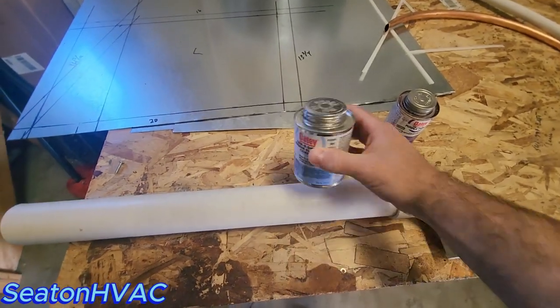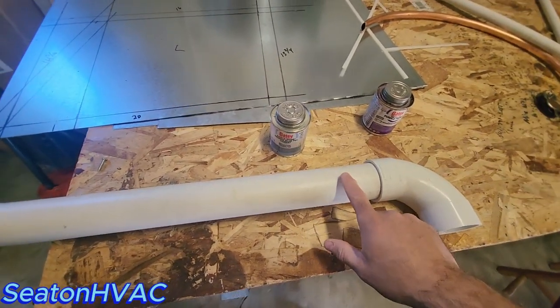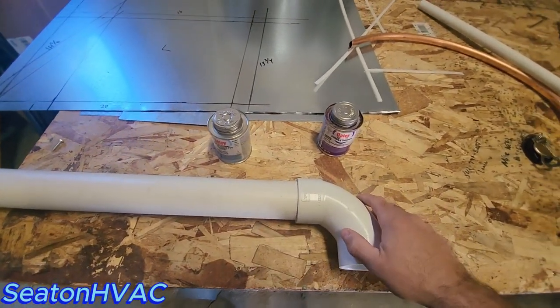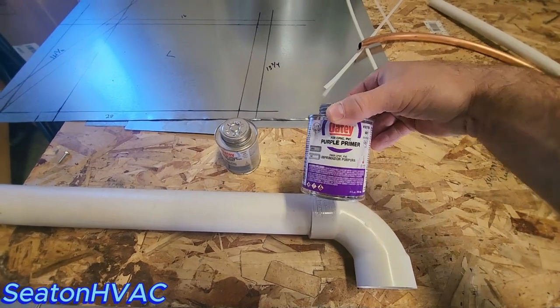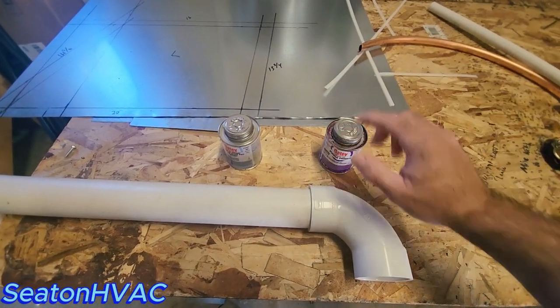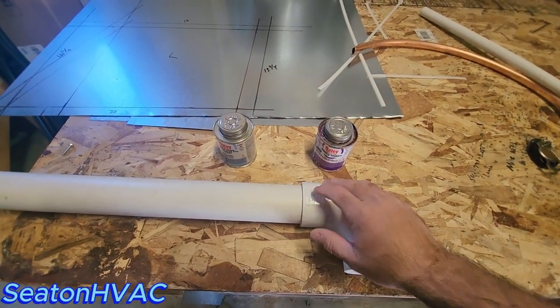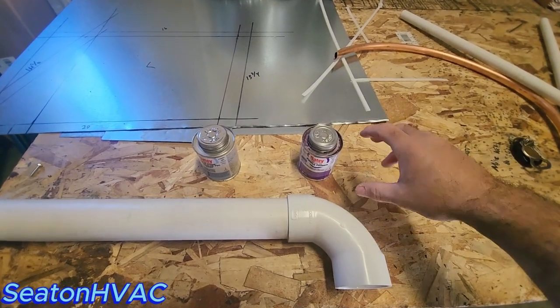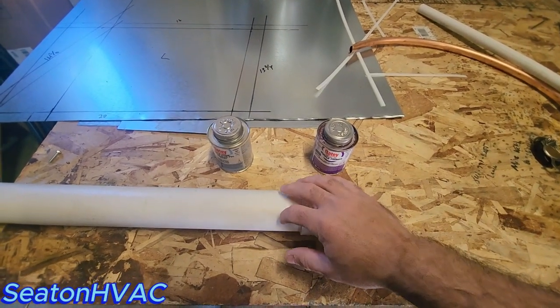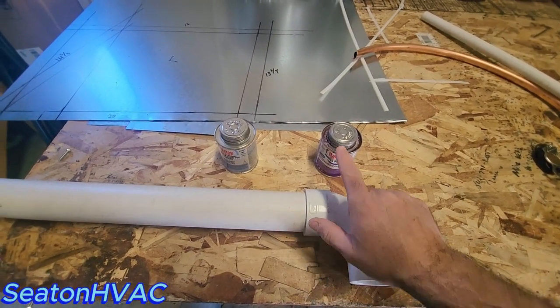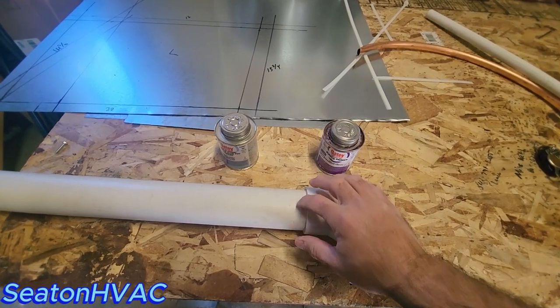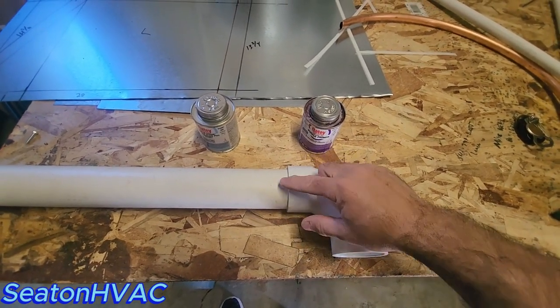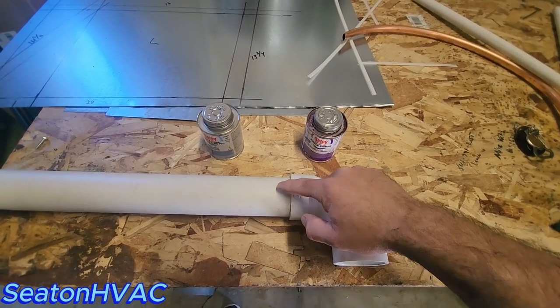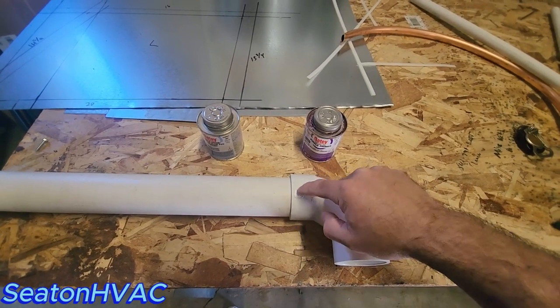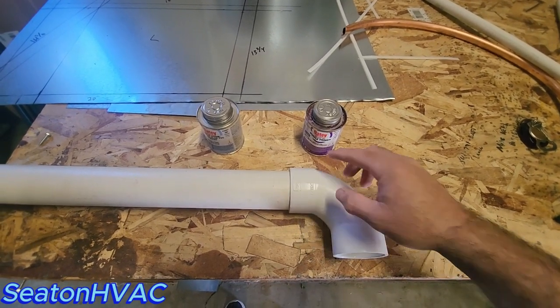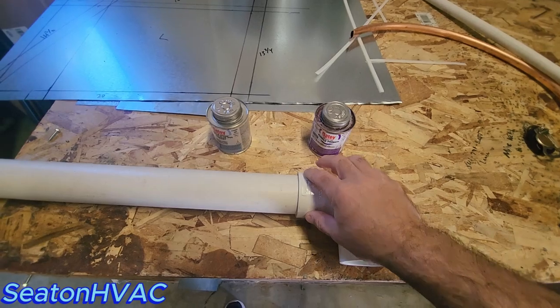For your vent piping on condensing furnaces—2-inch, 3-inch pipe—use the proper purple primer to prep and soften up your joints, then use the proper all-purpose clear PVC glue on top. Make sure your primer does not dry before you attach these. Primer the outside of the joint real good, and the inside of your female fitting, your elbow or coupling, whatever it may be.